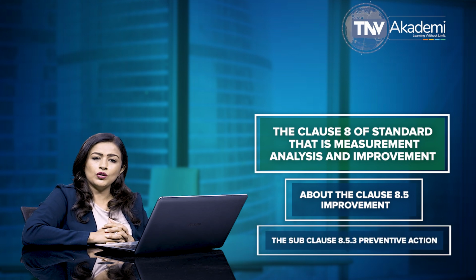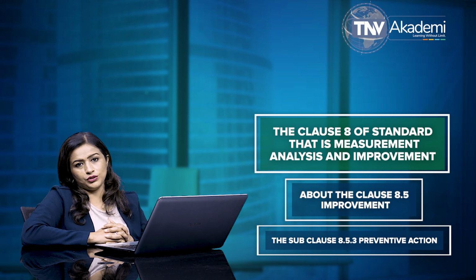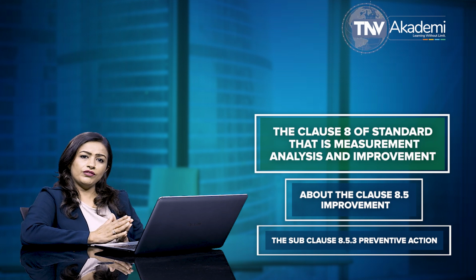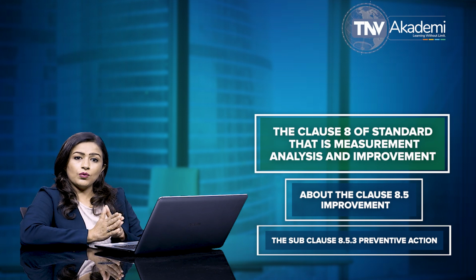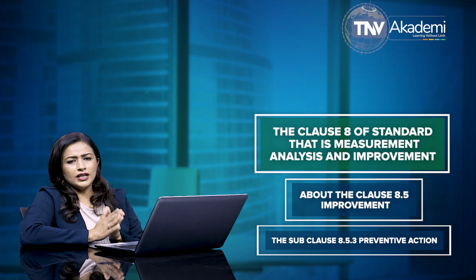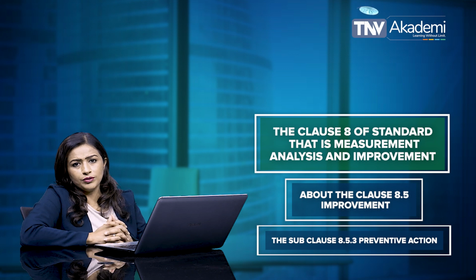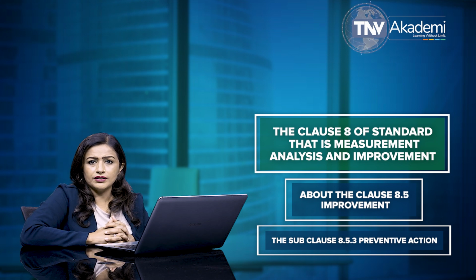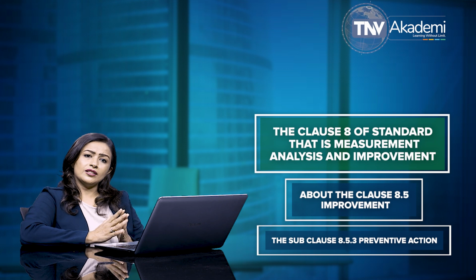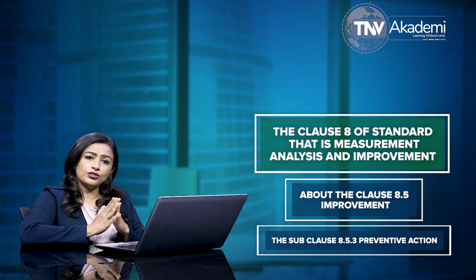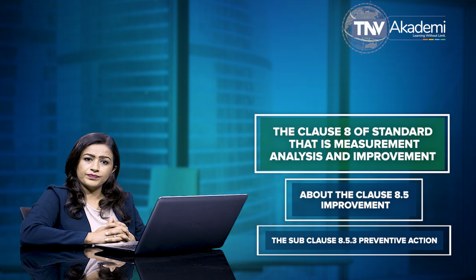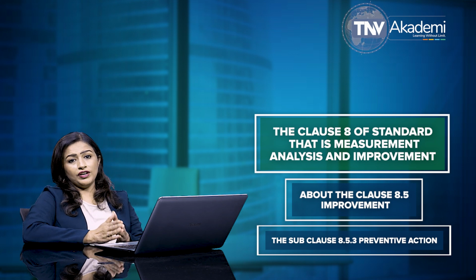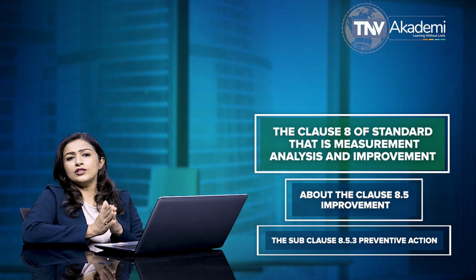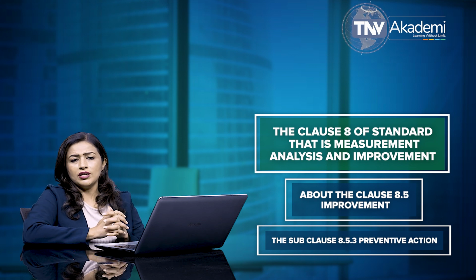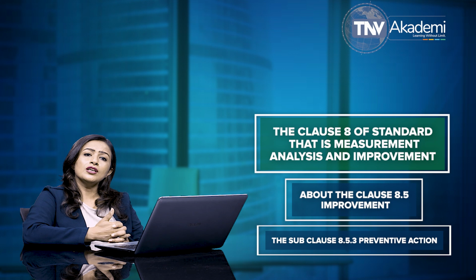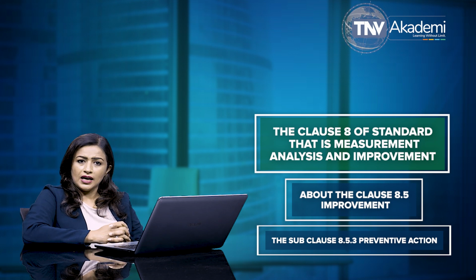Let us discuss subclause 8.5.3, preventive action. According to this subclause 8.5.3, the organization is required to determine action to eliminate the causes of potential nonconformities in order to prevent their occurrence. The subclause says that the preventive actions must be proportionate to the effects of the potential problems.